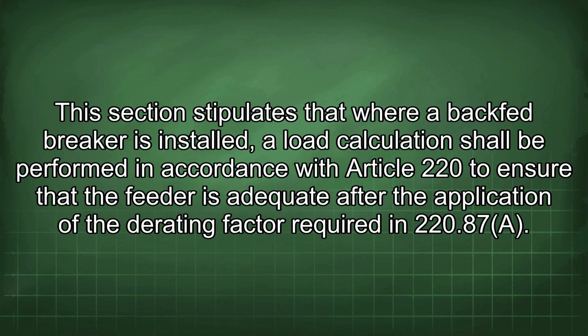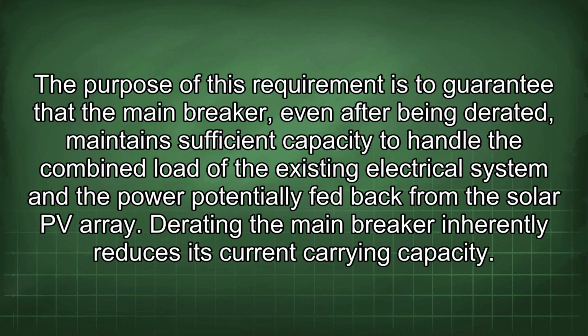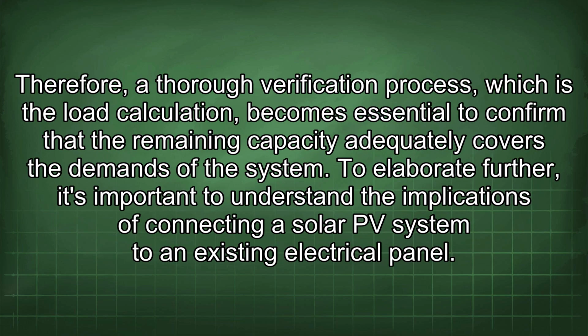in 220.87(A). The purpose of this requirement is to guarantee that the main breaker, even after being derated, maintains sufficient capacity to handle the combined load of the existing electrical system and the power potentially fed back from the solar PV array. Derating the main breaker inherently reduces its current carrying capacity. Therefore, a thorough verification process, which is the load calculation, becomes essential to confirm that the remaining capacity adequately covers the demands of the system.